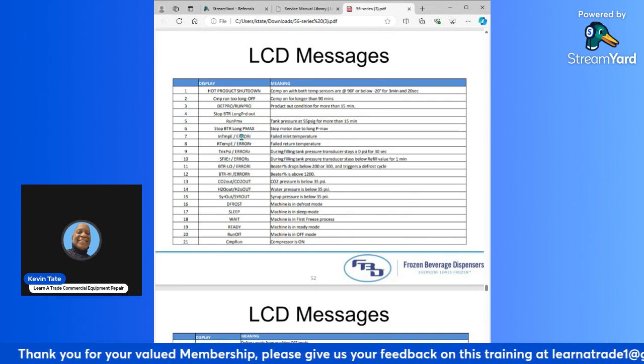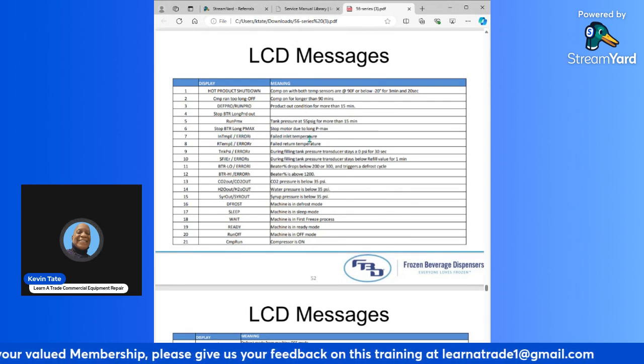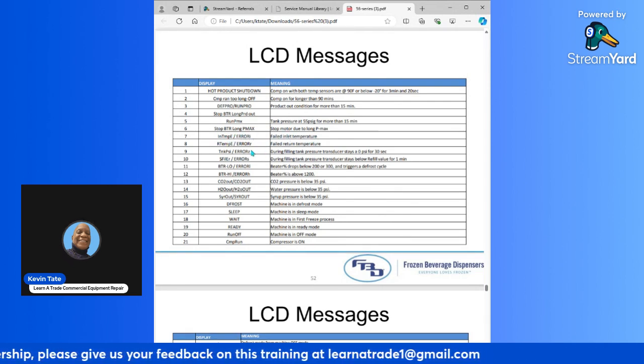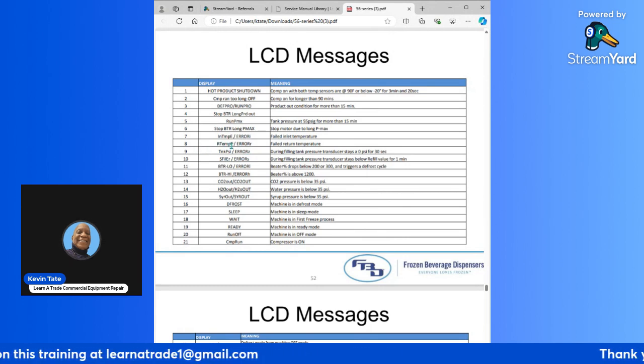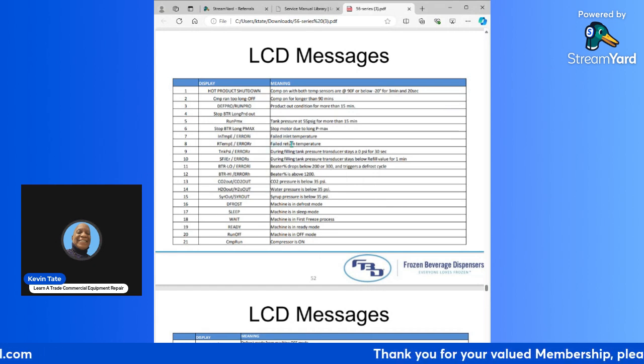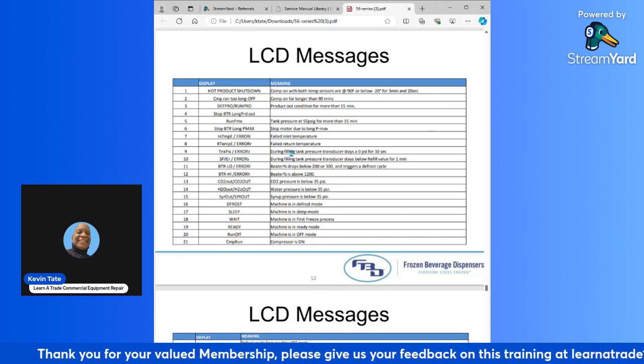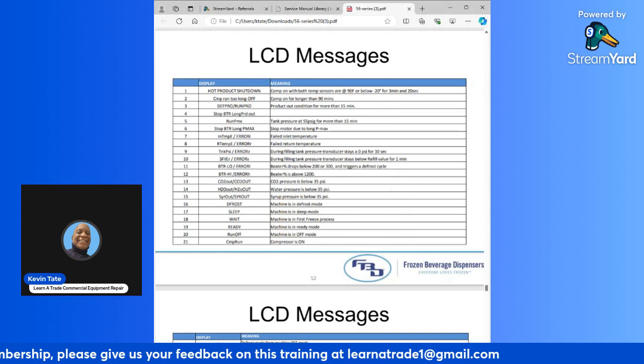Next is your in temp error. That's an error where you have a failed inlet temperature sensor. And next you would have R temp error. That R temp error means you have a failed return temperature sensor. Your tank PSI error is when, during filling, the tank pressure transducer stays at 0 psi for 30 seconds.